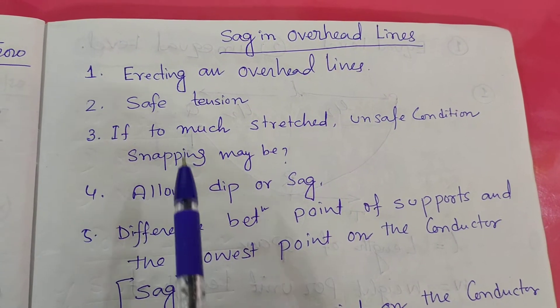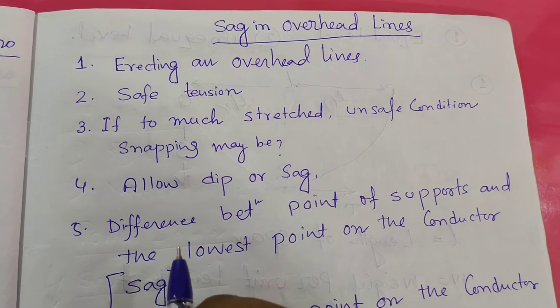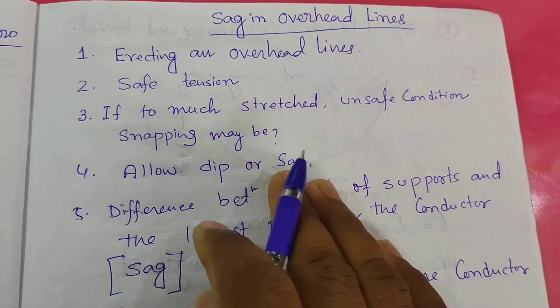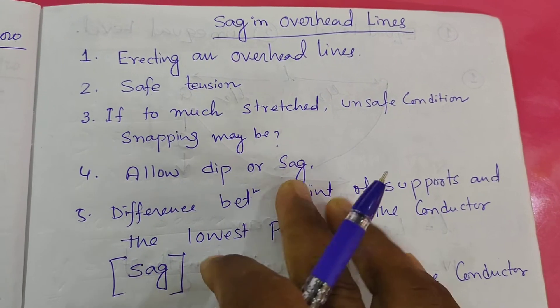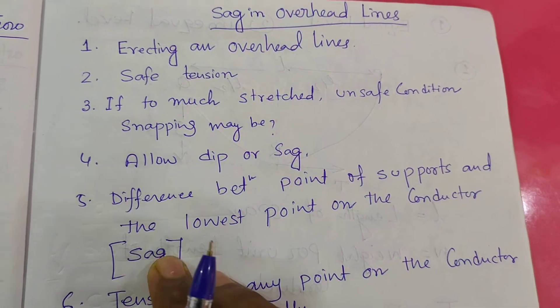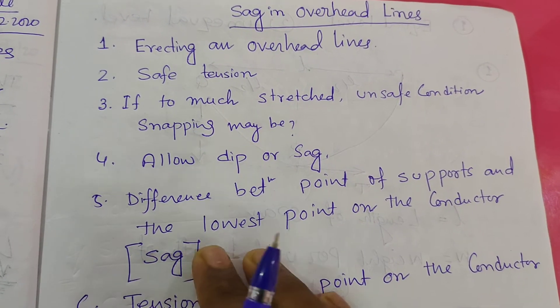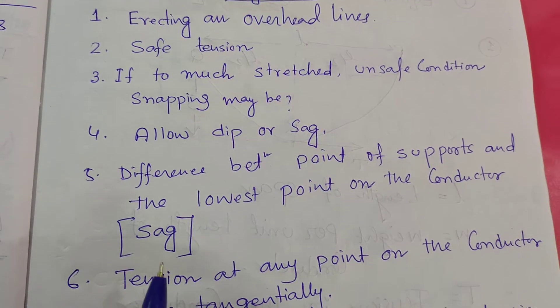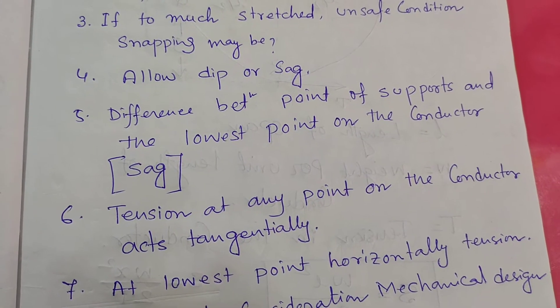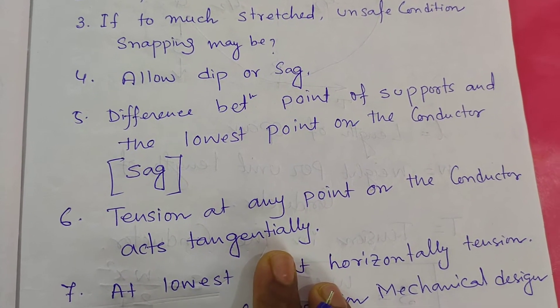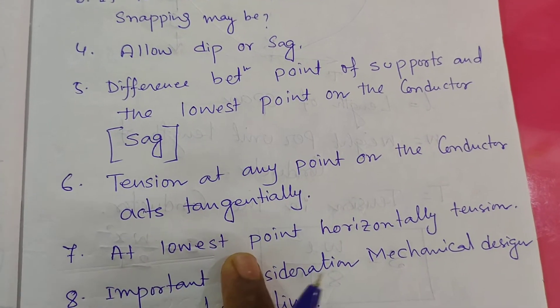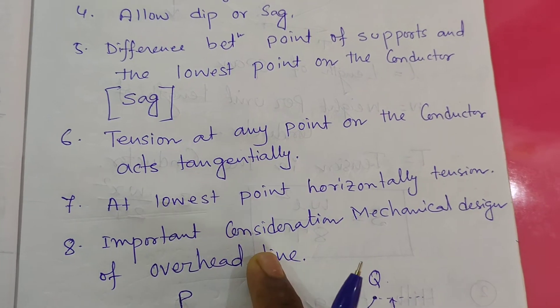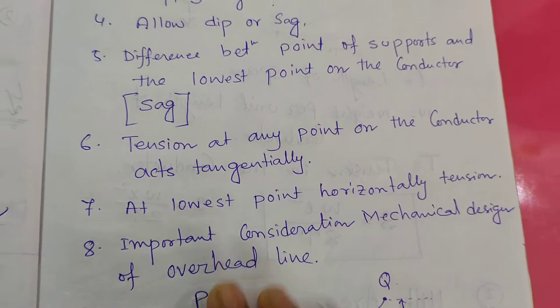It should maintain safe tension on the conductors. If too much stretch is provided, then unsafe conditions — snapping may occur and affect the SAG. The difference between the point of supports and the lowest point on the conductor is called SAG. The tension at any point on the conductor is tangential, and the tension at the lowest point is horizontal. This is an important consideration in the mechanical design of the overhead line.